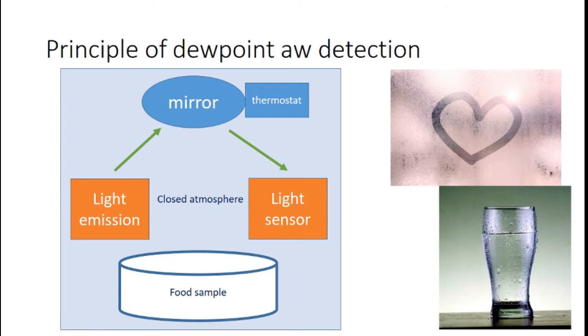The level of relative humidity is going to eventually condense on that mirror depending on the relative humidity in the closed atmosphere around this food sample and the temperature of the mirror. So that mirror is on a thermostat and the temperature slowly changes. Meanwhile, there's a little light sensor. It is pinging off a beam of light onto the mirror. The mirror is then reflecting it back onto a sensor.